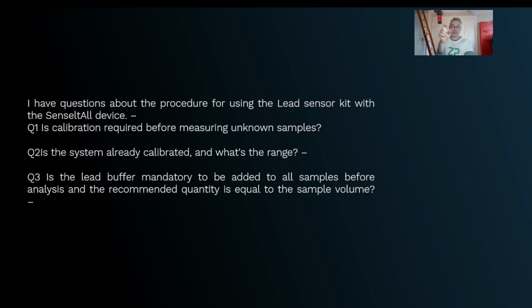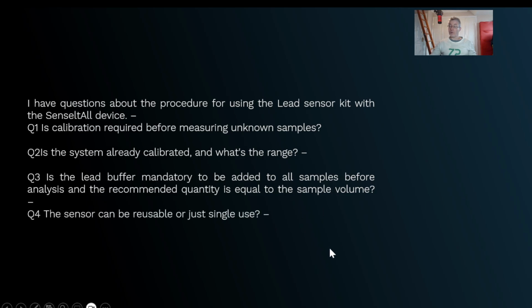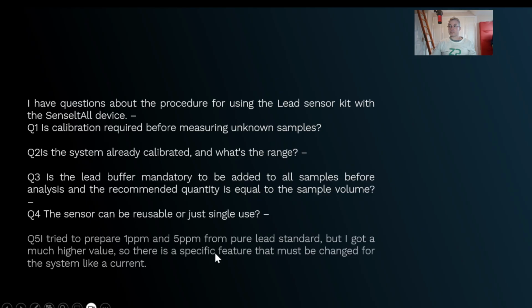I know you say, well, I don't know what that's going to be, but the system these days will actually just say high on occasion. So sometimes if there's too much lead signal, the result coming back will just say high, and that will encourage you to dilute more. Can the sensor be reused or just single use? It's just single use. At this point now, it's very hard for us to argue that we can get all of that lead and copper off that sensor.